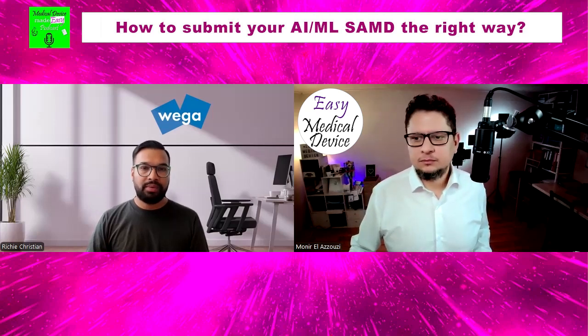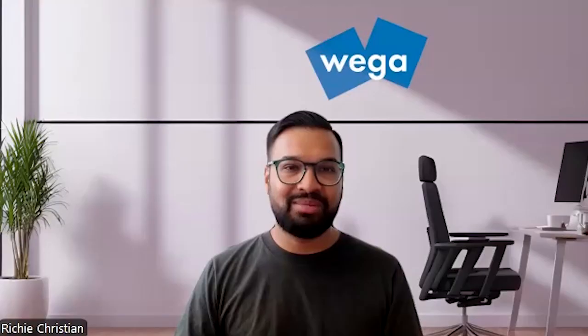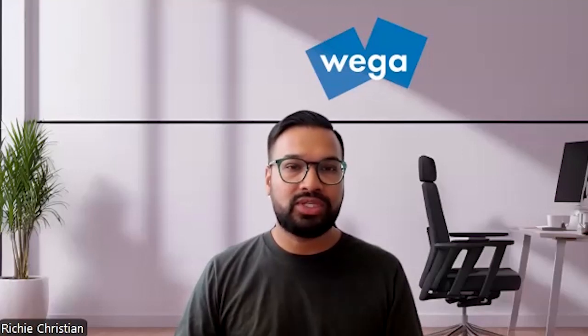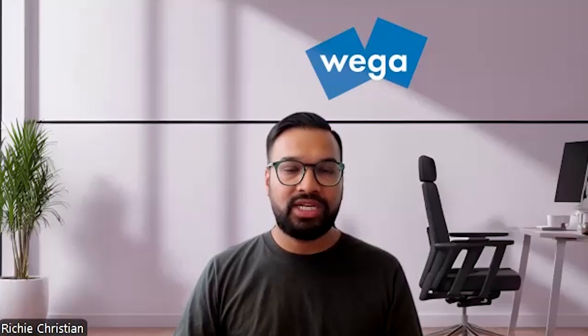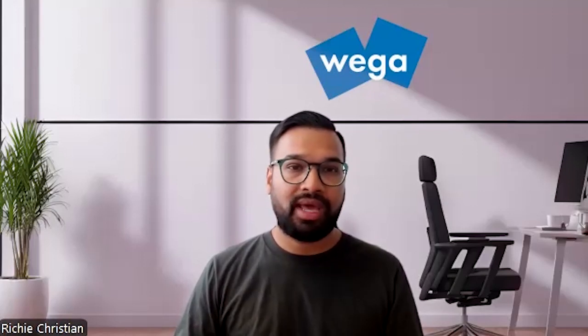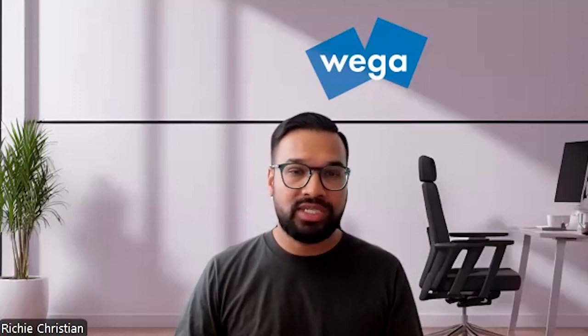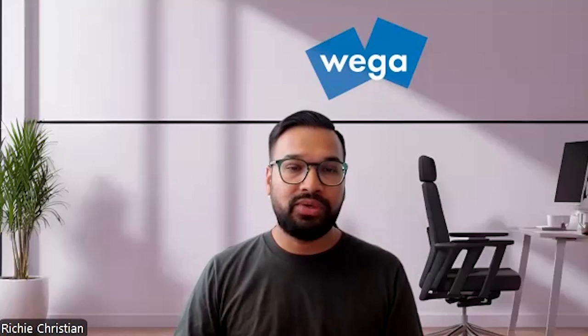When we talk about validation, I think this is one of the most commonly misused terms in the industry. There are so many types of validation. When we talk about ML model validation, we're really talking about clinical validation, that would be done as part of design validation, for example. This is where we are proving that the model is accurate and meets its intended purpose. If it's diagnosing something, that it actually is able to do that.